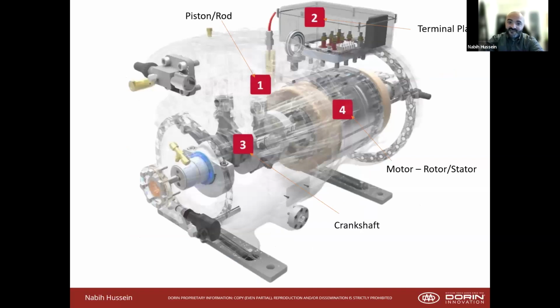Main things to know is the terminal plates. Your supply power goes into the compressor. It powers the motor, which is a rotor and a stator, which converts that electrical energy into mechanical energy through the crankshaft. That crankshaft, while it's spinning, it's moving the pistons, the rods and pistons, to compress low temperature, low pressure CO2 into high temperature, high pressure CO2. It gets accumulated in this discharge, and then it goes out to either your gas cooler or a condenser.